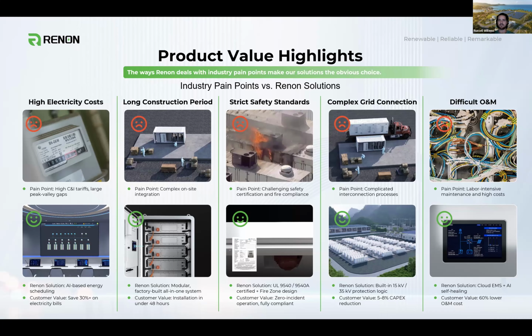That ties into the complexity of the grid connection. With this product especially, and several of our products, when we have an engineer on site to do grid connection and grid validation, we can complete grid validation and connection within a 24-hour period. If we have one person on site and the system is fully installed and commissioned, we can have support on site to validate the grid connection very quickly. Very little wiring is required. It's very handy that it's all built into that internal EMS screen, as I mentioned, and having that also extend to a cloud platform you can operate and interact with without being on site is another major advantage.